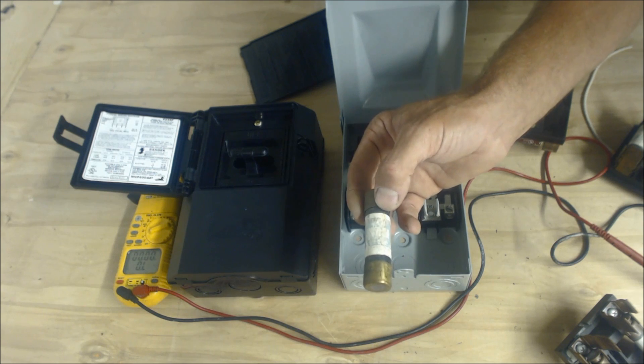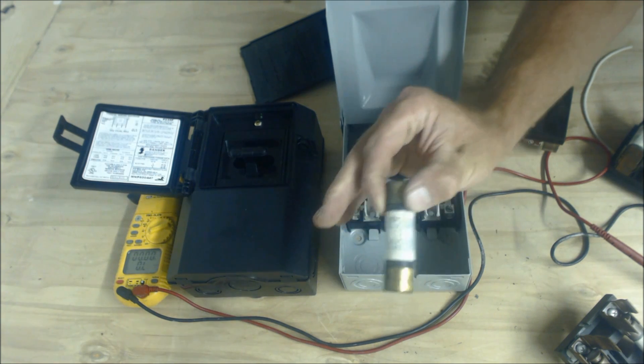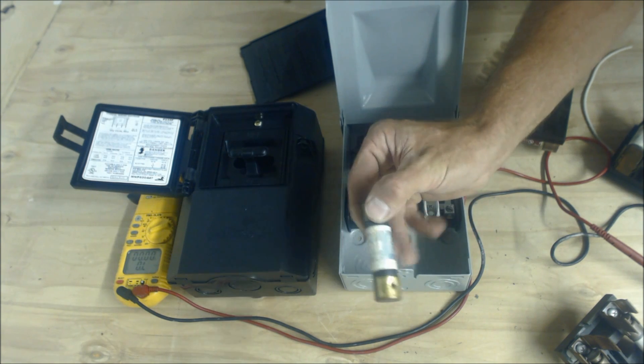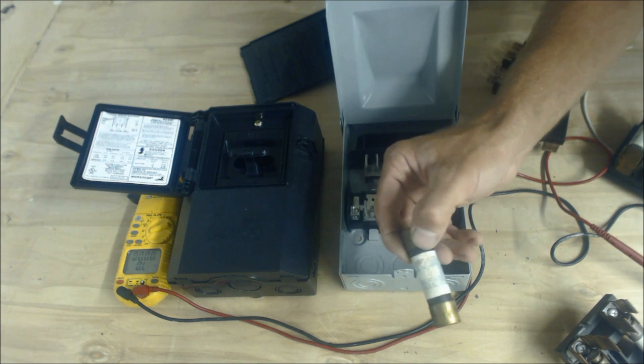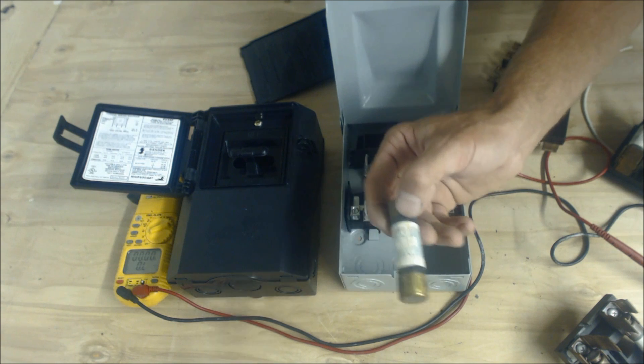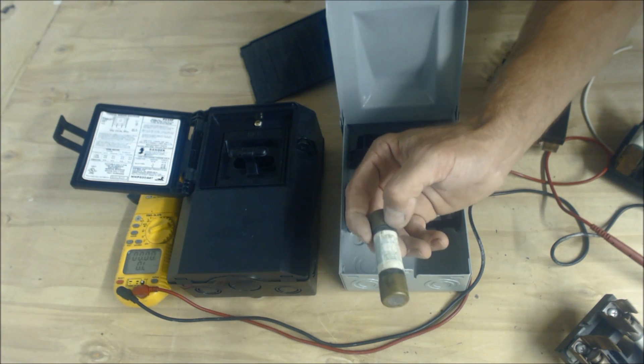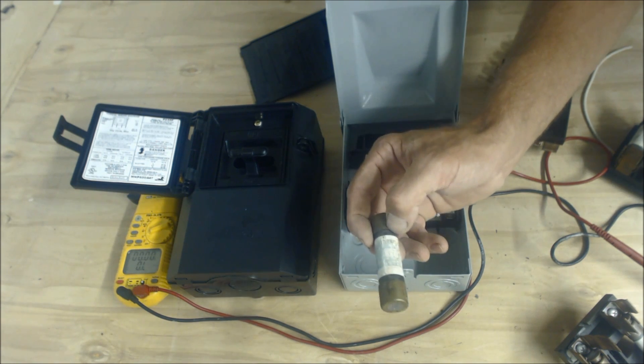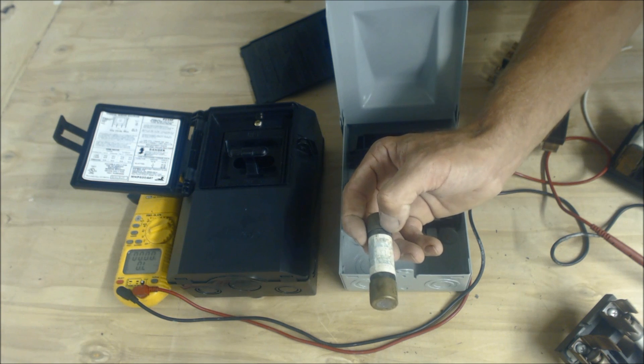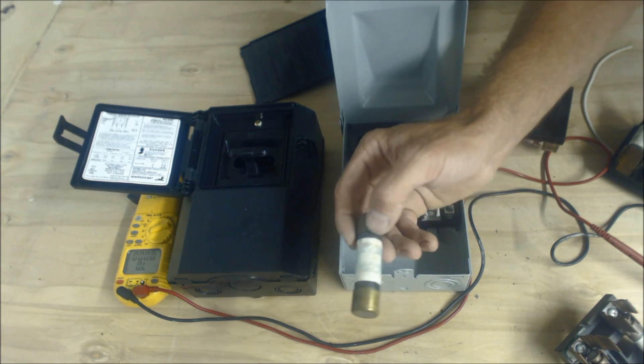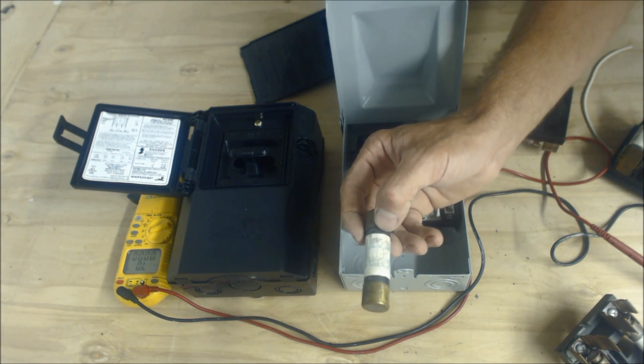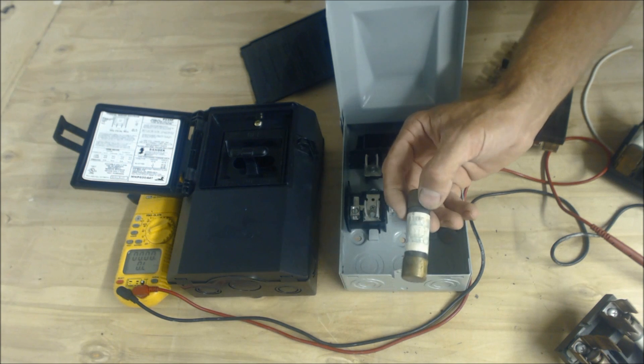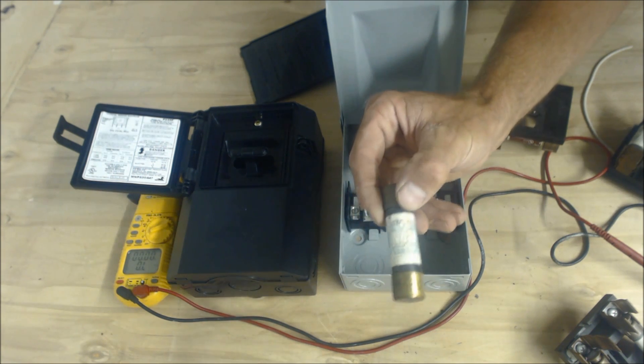Maybe, they are wearing down over time. A lot of those things are in place. So just for your own knowledge, it potentially could be nothing wrong with your system. Don't say, oh, no, my system is bad now or something like that. See what happens. Put that in, check the charge, check the amp draw, make sure the amp draw is not climbing, and you should be good. So I just want to make sure that you are aware of that.